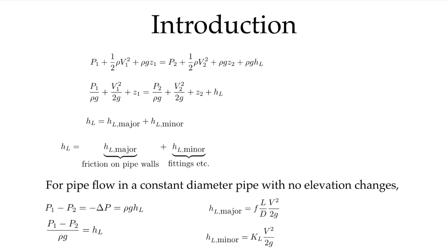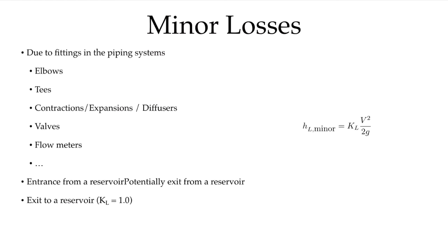Those minor losses come about due to all the other things on our piping systems: pipes changing diameters, elbows, T's or branches, diffusers distributing air into a room, contractions to smaller pipes, expansions to larger pipes, various kinds of valves, flow meters, and other instrumentation. Basically, anything that deviates from straight flow in a pipe where we have friction losses is going to give us minor losses.